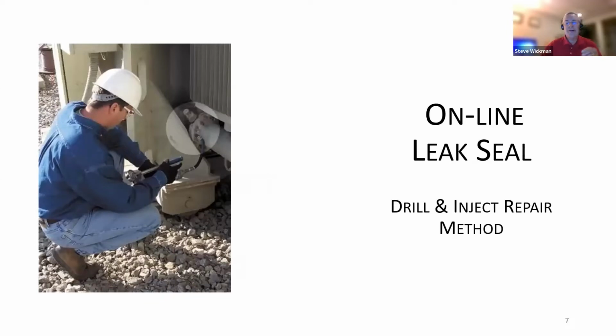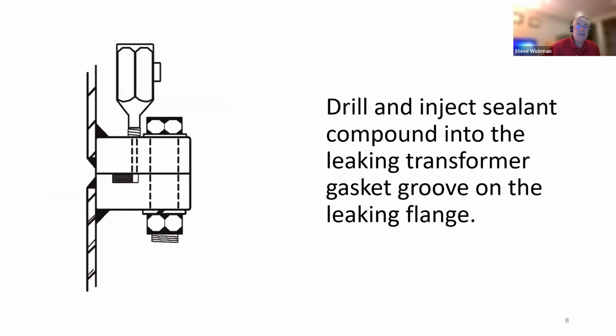We're going to talk first of all in this online leak seal arena here. The first commonly used technique is what's referred to as a drill and inject repair method. And this is basically as simple as merely finding the gasket groove, which we've got the skill and experience to do, and drilling access holes to it, tapping those, and then pumping a liquid sealing compound that cures to the same properties as a gasket into that gasket groove.